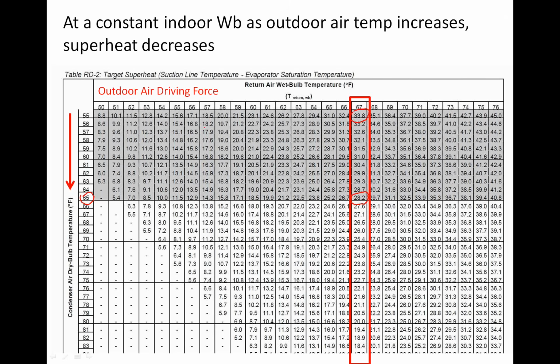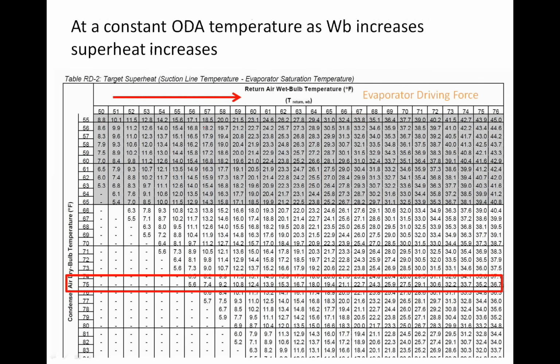Outdoor air is a driving force. So as the outdoor air temperature changes, the target superheat changes, right? And basically at a constant indoor wet bulb, as the outdoor air temperature increases, superheat decreases. That's a relationship you have to know. You don't have to remember it. You can look at your chart and you can see it right off your chart. If we take a look at a constant outdoor air temperature, right? So now we say, okay, well, what happens if it's just 75 degrees outside?